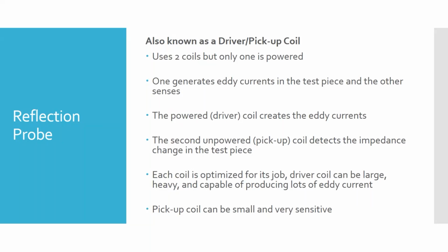These are very sensitive and very good for that, but it's a more expensive coil. Older eddy current testers weren't able to do this—they didn't have two channels, no way to send power on one channel and receive information on the other.